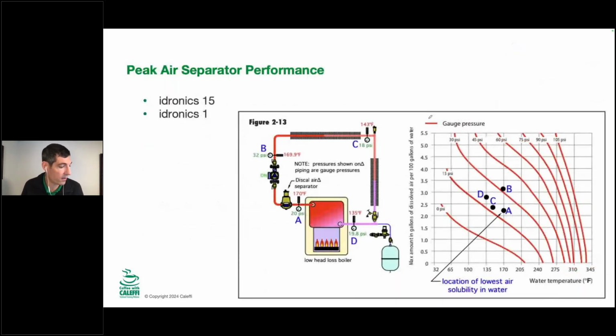So the location of these devices, an air separator, we want it in the hottest, lowest pressure spot. This is a lot more detailed than I'll go into in this presentation, but the hottest spot on the outlet of the boiler before the circulator is where we're going to have the lowest solubility of the air in the water. So it's going to come out of solution and we're able to vent it. If we put that in position B, the pressure just went way up because we boosted it with the circulator. So the temperature is still hot, but we kind of force all those air bubbles to go back into solution, and we can miss them and they'll come back out of solution somewhere else in the system.